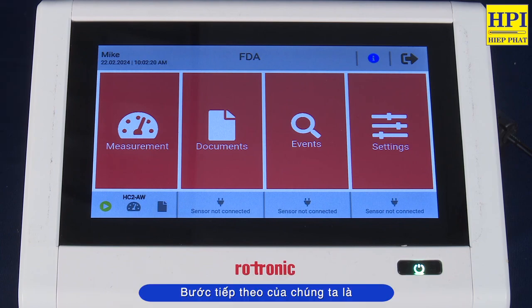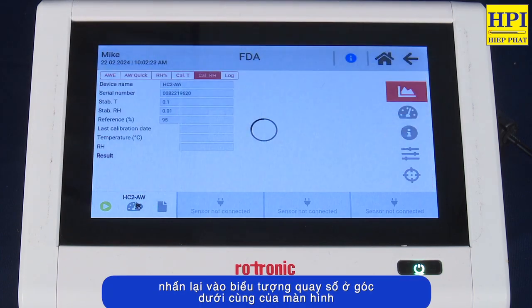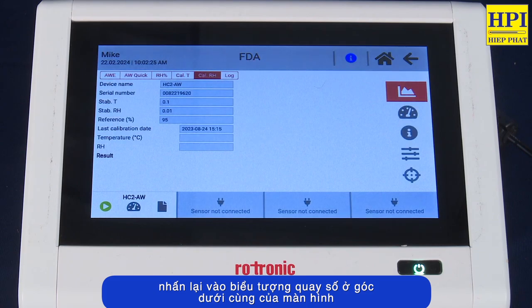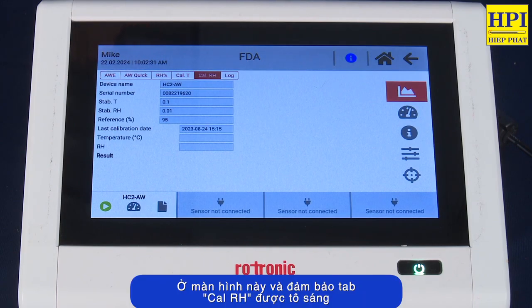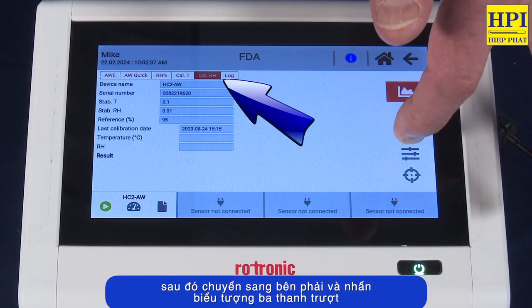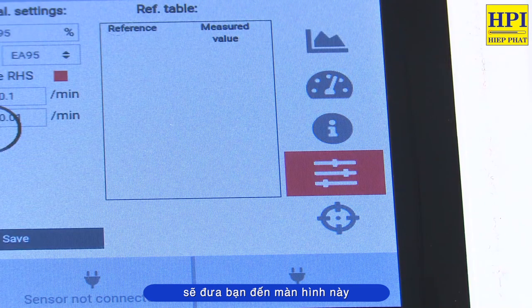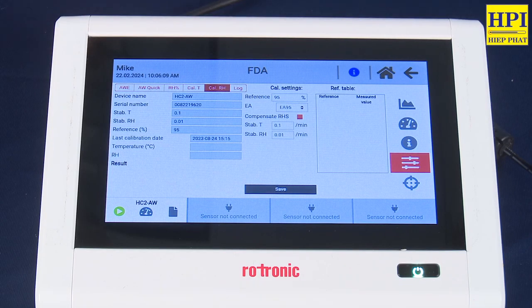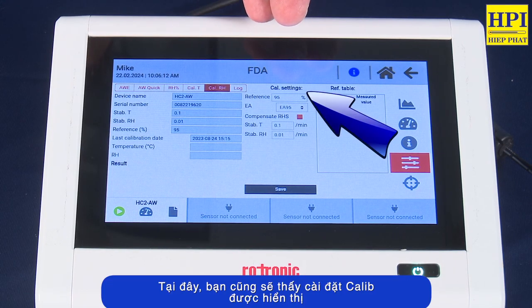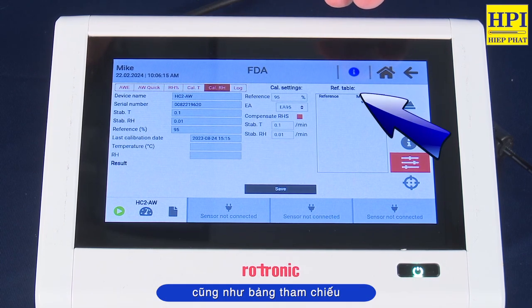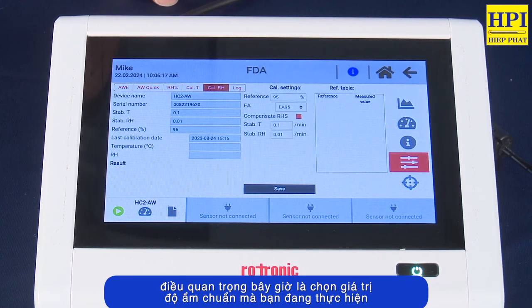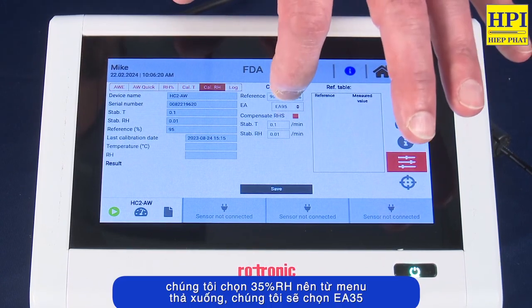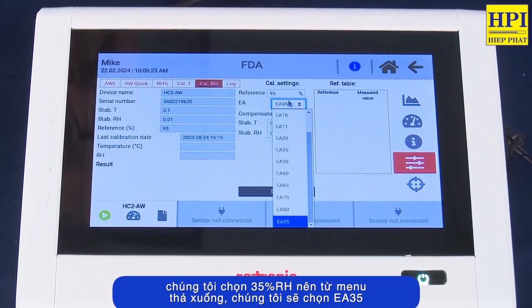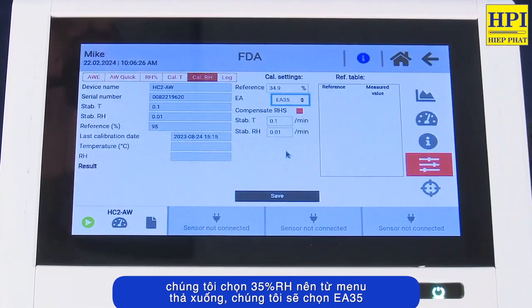Our next step is to press the icon with the dial, again, at the bottom left-hand corner of the screen. You'll now be brought to this display, and you want to make sure the Cal RH tab is highlighted. You will then go to the right hand and press the 3 sliding bar icon, which will bring you to this display mode here. You'll see Cal settings displayed, as well as the reference table. It's important now to select the humidity standard that you've chosen. In this instance, we've chosen a 35% RH, so from the drop-down menu, we're going to select that.